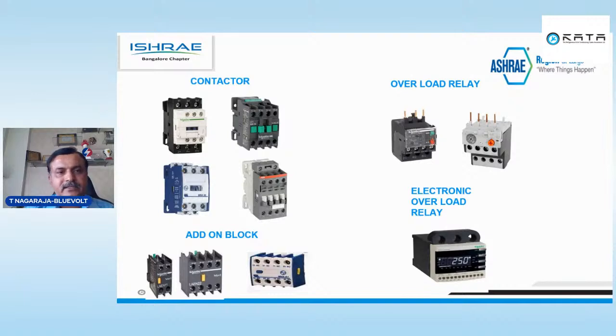Then these are the contactors for switching purpose. Maybe different makes, different varieties, different ampere ranges are there, from 6 amps up to whatever current rating we require, we can select accordingly based on the motor kilowatt. For that, add-on blocks will be there for the control circuit. These add-on blocks are 1NO, 1NC, then 2NO, 2NC, you can go 4NO, 4NC. Accordingly, for your control circuit, trip indication, and on, off indication, depending on how many auxiliary contacts are required, we can select.